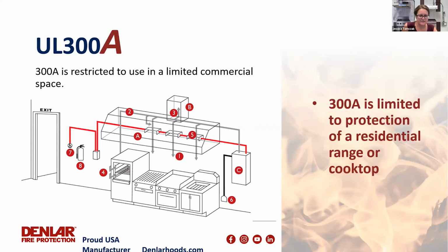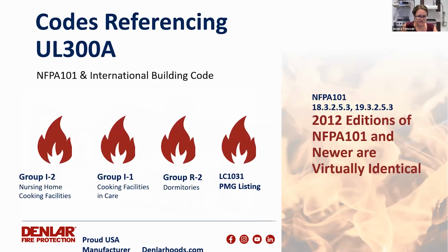And in order to be tested to UL 300A standards, we have to go through a rigorous testing process. There's several tests that have to occur with pots and pans of oil on fire, and we have to wait for the system to put out that fire. So it's quite the process. There's no draft, the fan can't be on, and we're installing it just like it would be in the field to do that testing. So just a little bit more about what that takes to be listed there.